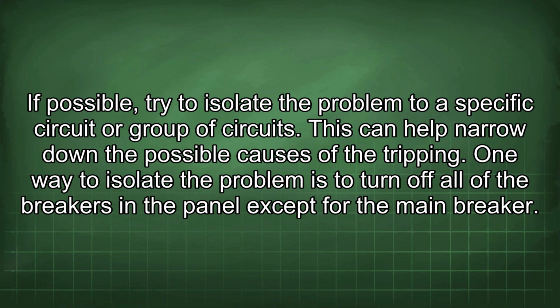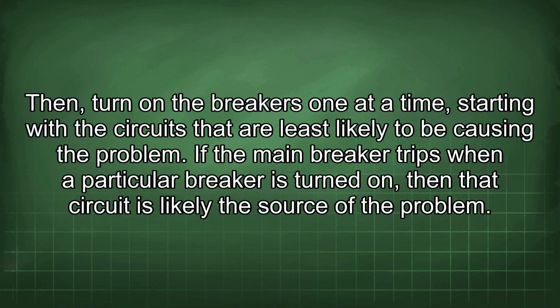One way to isolate the problem is to turn off all of the breakers in the panel except for the main breaker. Then turn on the breakers one at a time, starting with the circuits that are least likely to be causing the problem. If the main breaker trips when a particular breaker is turned on, then that circuit is likely the source of the problem.